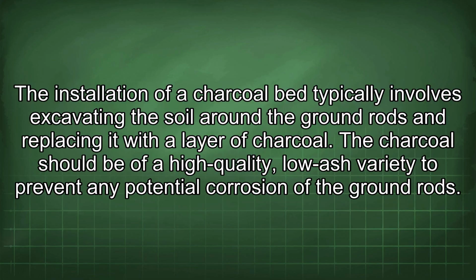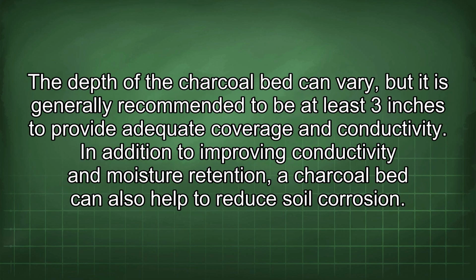The installation of a charcoal bed typically involves excavating the soil around the ground rods and replacing it with a layer of charcoal. The charcoal should be of a high quality, low ash variety to prevent any potential corrosion of the ground rods. The depth of the charcoal bed can vary, but it is generally recommended to be at least 3 inches to provide adequate coverage and conductivity.